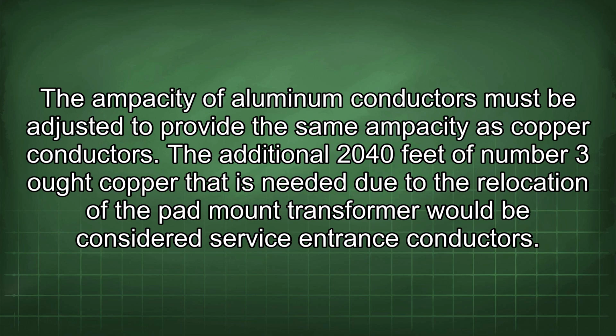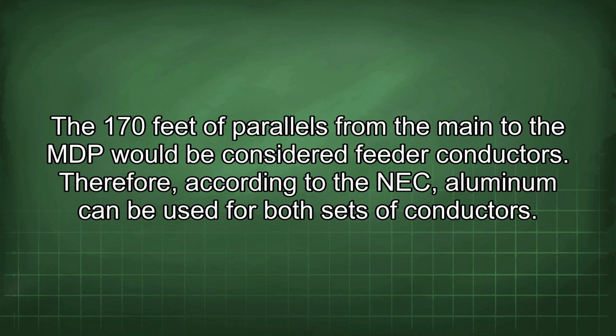The additional 20-40 feet of number 3/0 copper that is needed due to the relocation of the pad mount transformer would be considered service entrance conductors. The 170 feet of parallels from the main to the MDP would be considered feeder conductors. Therefore, according to the NEC, aluminum can be used for both sets of conductors.